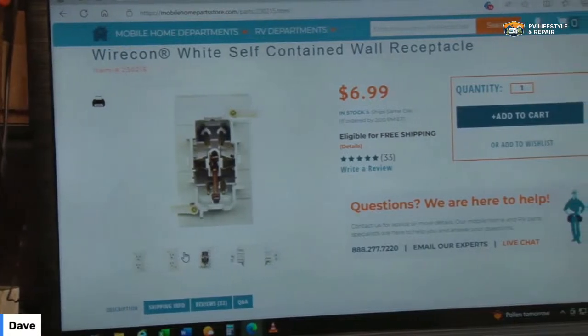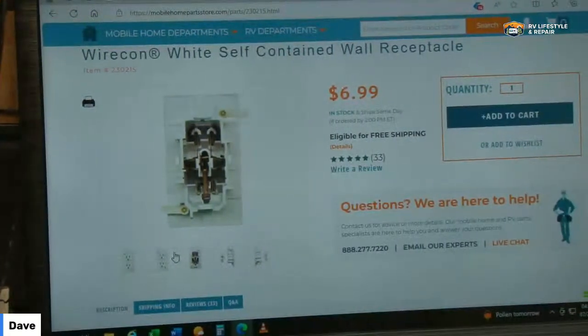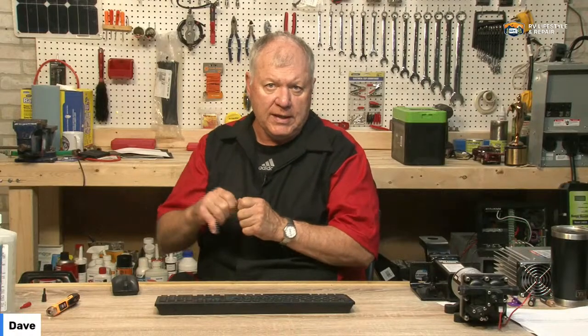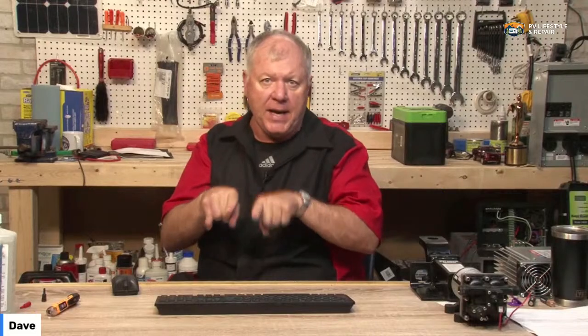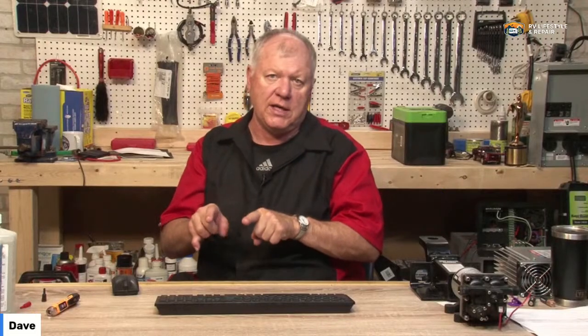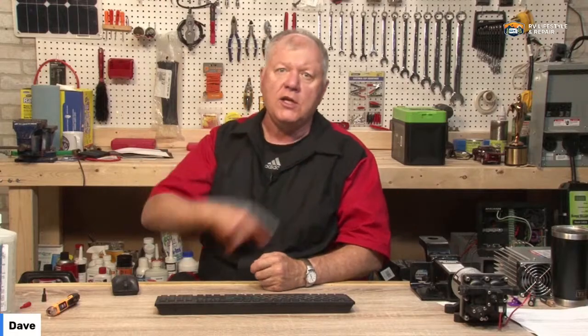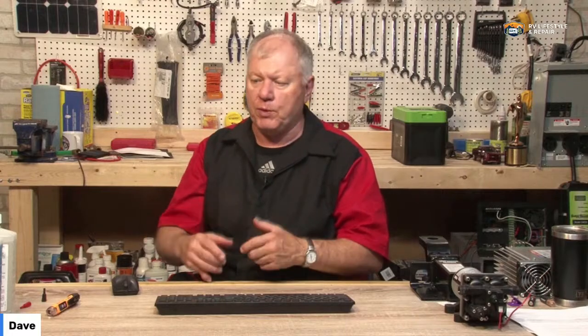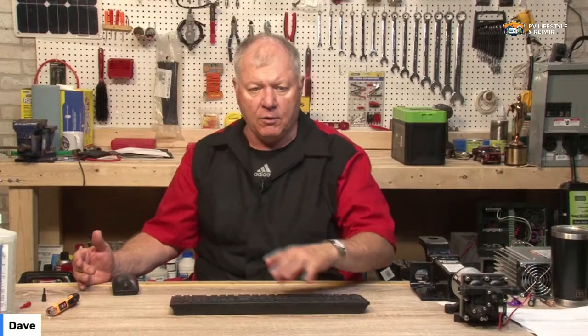They're cheap and they look good, and when they're in a house that's fine because you slide them into that spade and they hold, since your house isn't going to bounce 60 miles an hour down the road. But I've seen many of these where the wire has literally pulled out because of the vibration you get in RVs. I like to take the residential style that has a screw - you put a loop around it, put the screw in, tighten it down. You do not use the push-ons in the back; some of them have those, and they don't give you a good connection, they don't stay in place. Once you get those screws installed, tape it really good around the whole body with black electrician's tape. I do not like those WireCon - I didn't know that's what they call them, we always call them spade or push down receptacles. I'd definitely get a different type of receptacle for that.